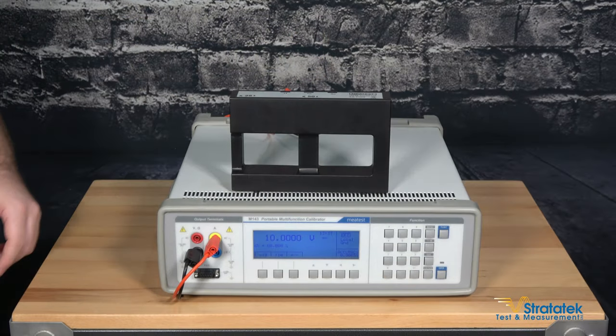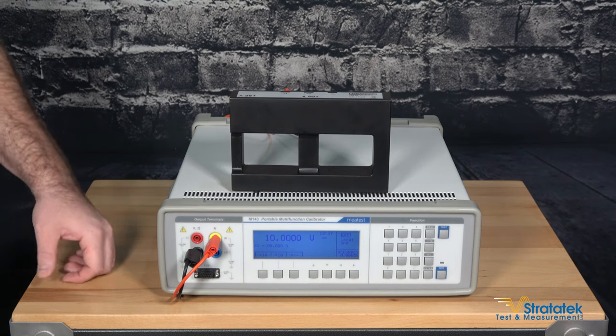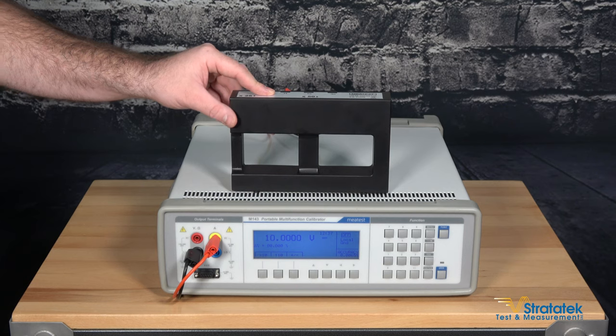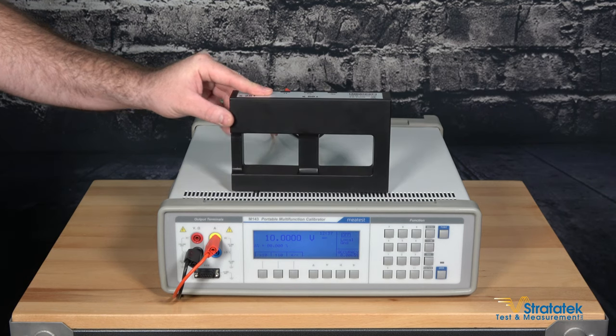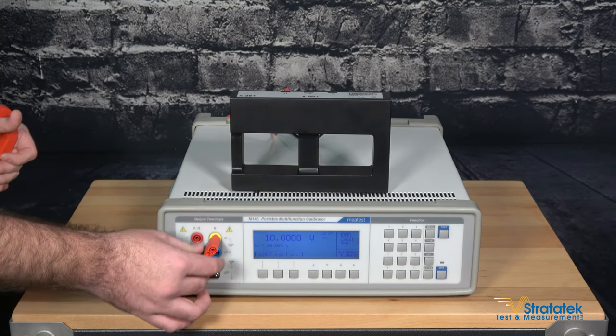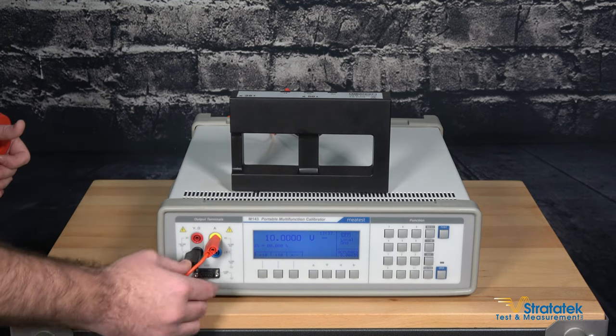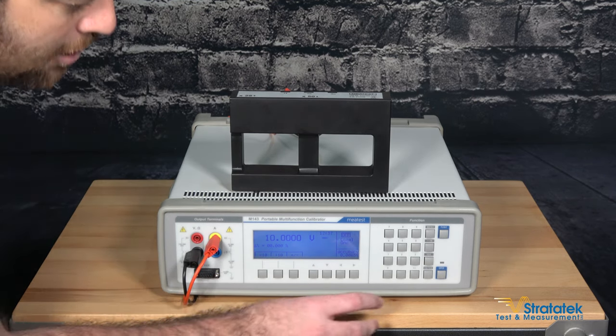Now I'm going to show you calibrating a Fluke clamp meter with the M143 calibrator in tandem with the 140-50 current coil from Meatest. We've already made our connections using the banana test leads into the times 50 pole, so let's set up the calibrator for the measurement now.